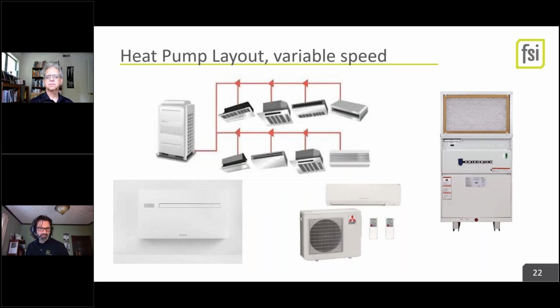This slide is fancier units with variable speed compressors. Their compressors work at a lot lower temperatures. I'll show you some graphs in a minute. But that bottom left corner, we got so much interest in that dual duct through the wall unit. That's what it looks like hanging on the wall. Little teeny unit. VRF, and then Friedrich makes the variable speed vertical package heat pump. Next slide.